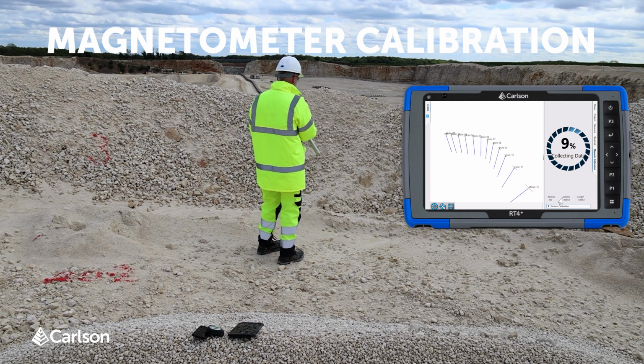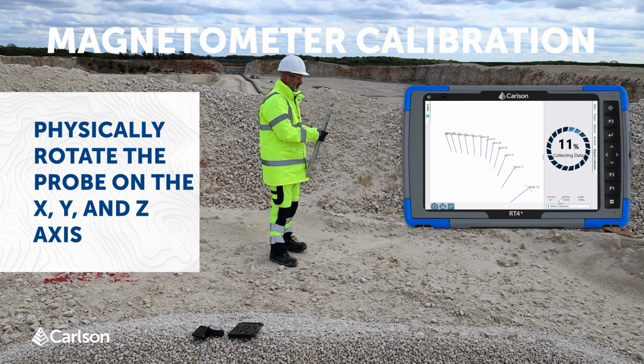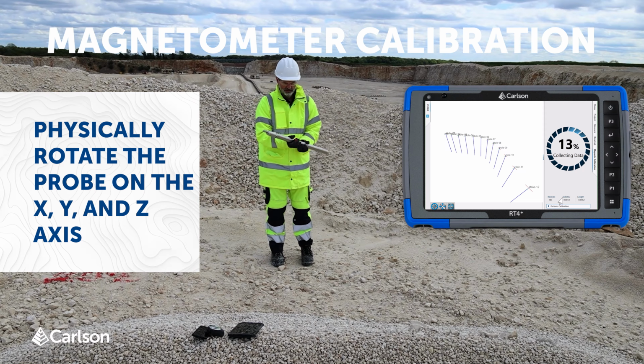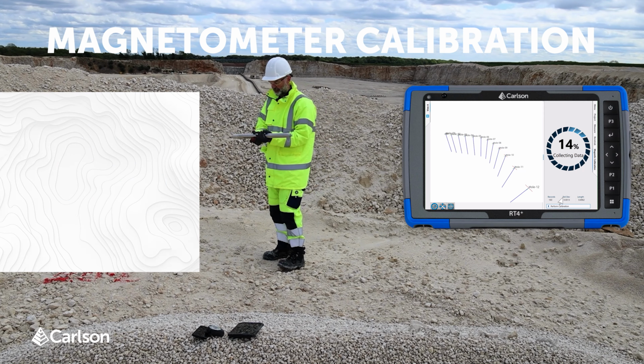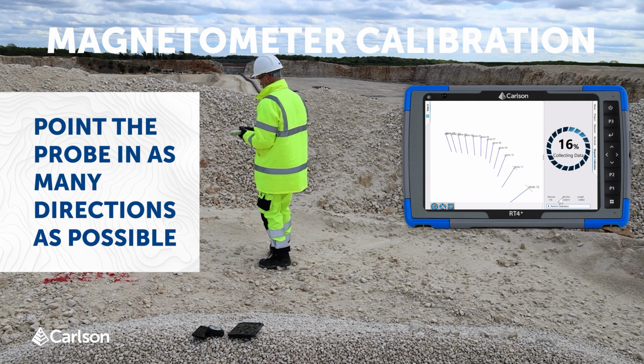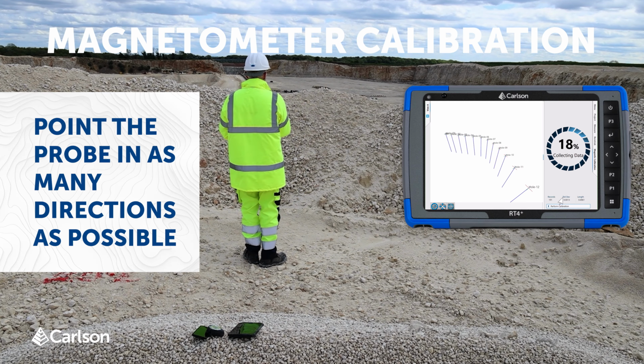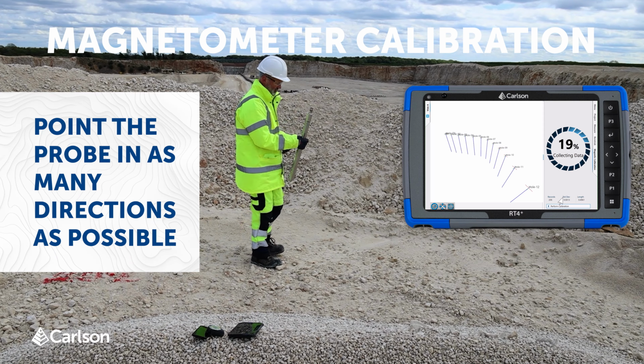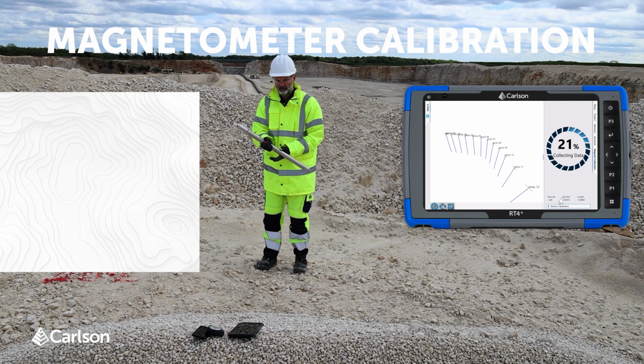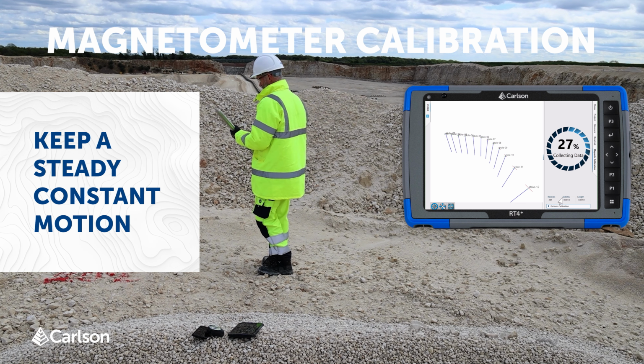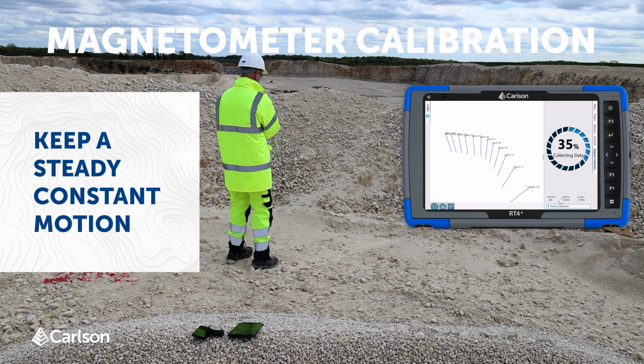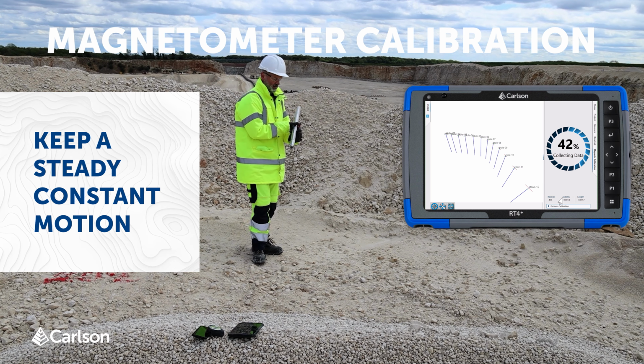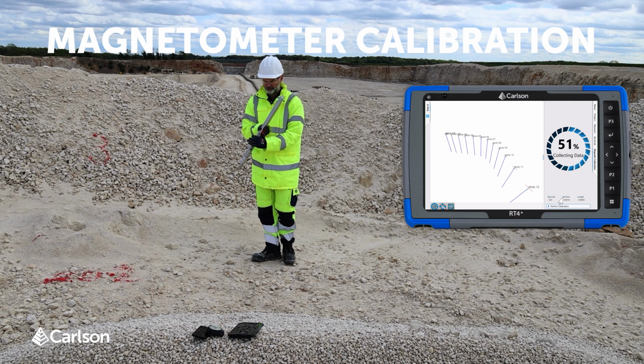Your aim during the calibration is to physically rotate the probe around all three axes. Imagine a 360-degree sphere around the probe. The intention is to point the probe to as many different points on that sphere as possible. While the calibration is in progress, data points are being collected approximately 10 times a second. Keep a steady, constant motion as the calibration data is being collected.